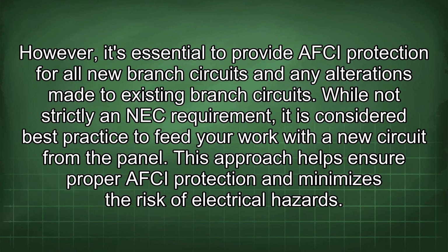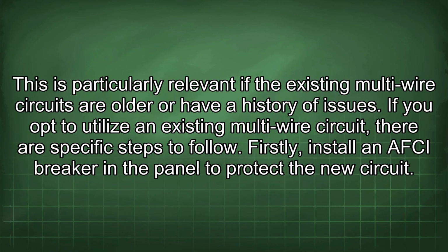While not strictly an NEC requirement, it is considered best practice to feed your work with a new circuit from the panel. This approach helps ensure proper AFCI protection and minimizes the risk of electrical hazards. This is particularly relevant if the existing multi-wire circuits are older or have a history of issues.